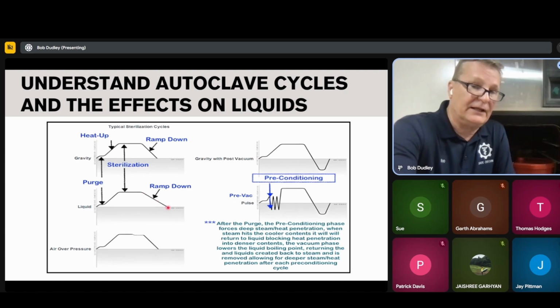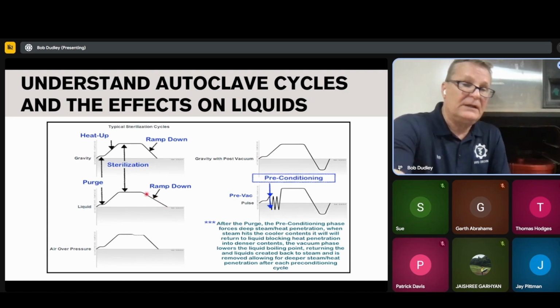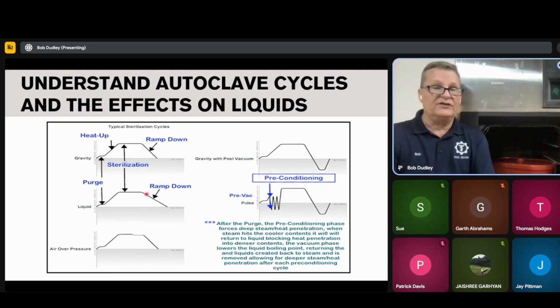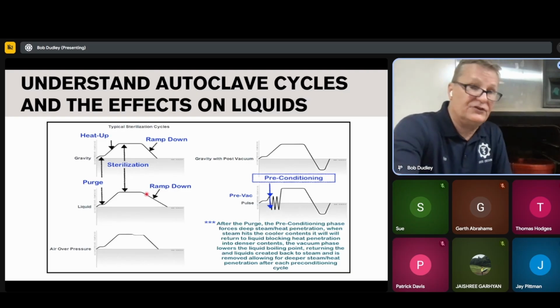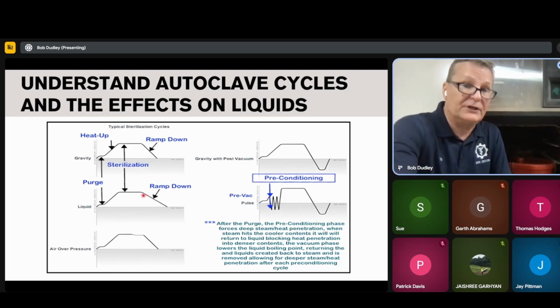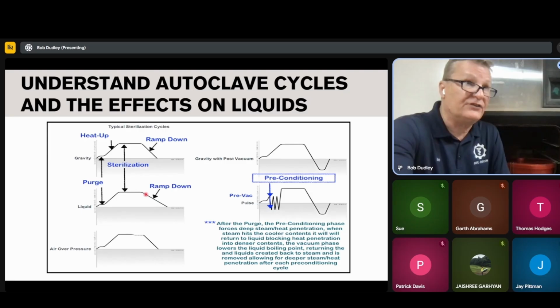If you're losing, and I'm just going to give you this advice, if you are losing more than 10% of your water on your liquids and your media is blowing up and you're getting this mess in your autoclave, then it's either one or two things. Either this ramp down timer is set too low, and you need to increase it. And some people will do them at 1.5 minutes. I tell everybody between 2 and 3, and then let that ramp down.